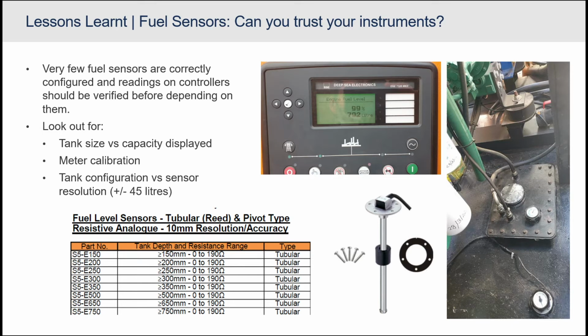What happens then is, if you look at the display, it will tell you, for instance on this one, it's got almost 800 liters in. And if it falls below that, it will give you the indication of how much is left. Quite often people want to use that information when refueling is done, to verify the amount of fuel that's been put in compared to the invoice that you get. And quite often you can't use this information, so it actually puts you in an awkward position. You just have to approve whatever the guy charges you when it comes to refueling. So the first one is the tank capacity versus the displayed one.